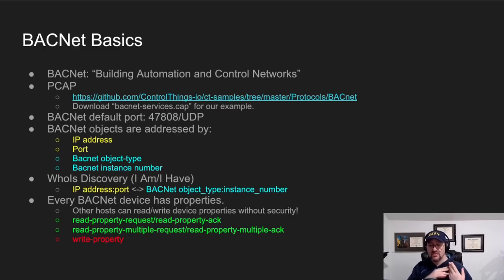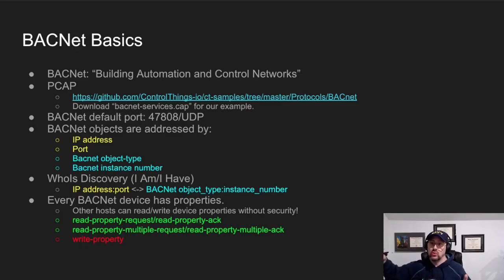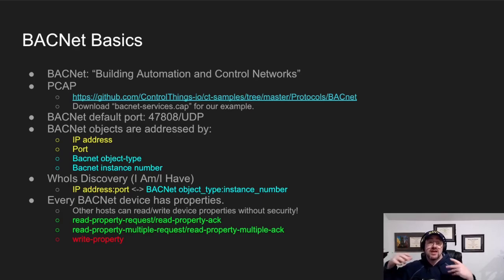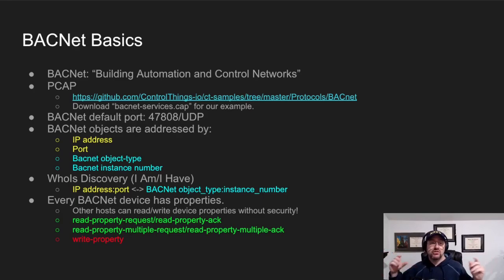In the IP world, networks are segregated by the pair of IP address and port. You could have a firewall that on port 47808 routes packets to BACnet network A, and on 47809 routes packets to BACnet network B. That's how I've seen organizations keep their BACnet networks separate — by using different IP address and port combinations.